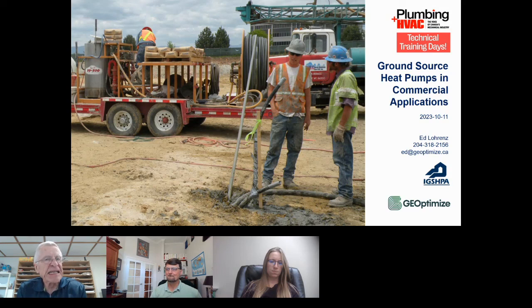With electric auxiliary that is available from most manufacturers, that electric coil is downstream of where the heat pump is, and it only is used as it's needed. That's correct. I think the furnace manufacturers don't want the coil before the heat exchanger. They want it after, so it doesn't cause as much problems with them. But certainly dual fuel in a residential application has been done quite often, especially if people have a marginal electrical service panel to their home, and maybe they don't have enough power to run a lot of electric backup with the heat pump. You could use a dual fuel system like that to augment the system that way.